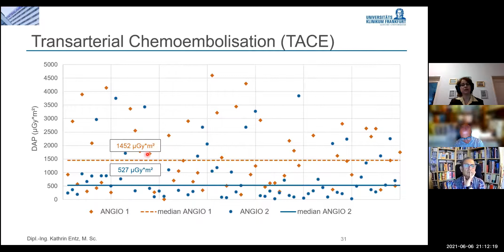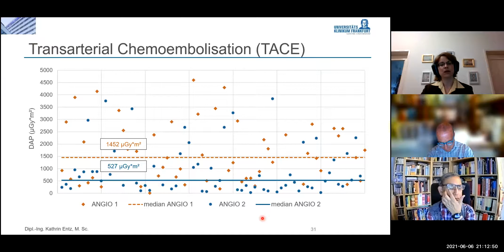But let's have a closer look at the values down there. And you can see that the values here from system 1 have a mean value of roughly 1,500, while system 2 only has 500. So there's a difference of factor of 3. And again, by looking at this graph, you can find out that you have to optimize the system here, Angio system 1, while this is much better. The problem in this case was that Angio system 1 is an older system, so we do not have really much we can optimize in this case. So the only thing we can do is to try to use the second system more, because it can work with lower doses, especially when we are working on children or younger patients. Then it is better to use system 2, which is working with lower doses.